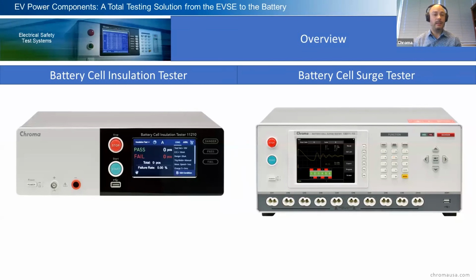The other one is our battery cell surge tester, which is designed to test the insulation quality between the positive and negative plates of a lead-acid battery cell. Basically, what we do is apply a high voltage surge impulse before the electrolyte injection process, effectively decreasing the defective rate in production. We've given this product an output voltage that can go up to 6 kilovolts. It has a 4-terminal measurement and a sampling rate of 2 megahertz. So again, I'm going to go in depth into all the different modes and testing methods that these products have, especially for the cell tester. We have a couple of other applications that are not pertinent to this webinar.